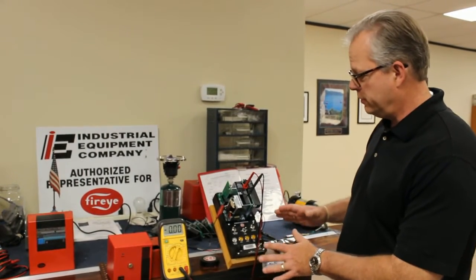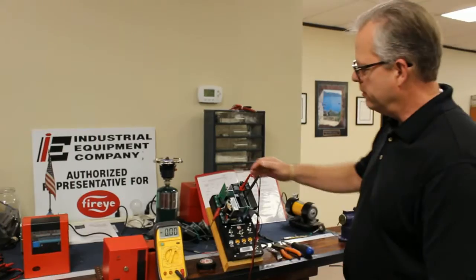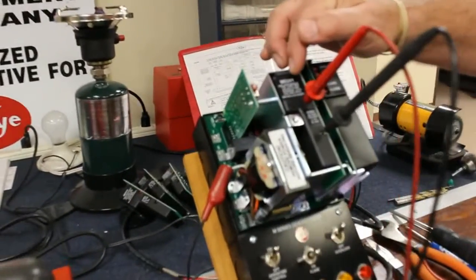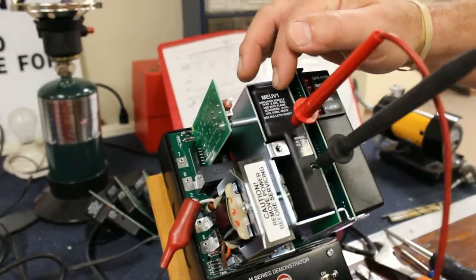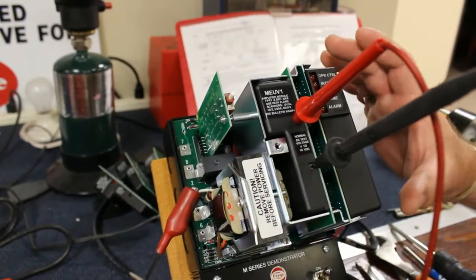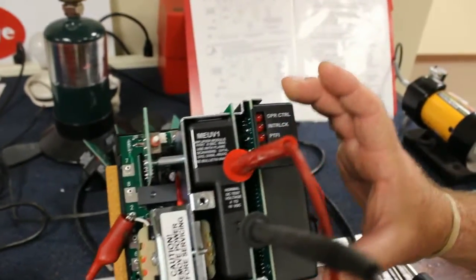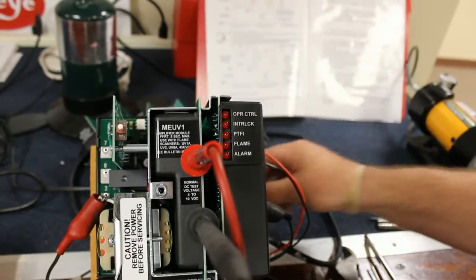but before I do, I'm going to talk about what we have here. We have an MEC120 chassis, an MEUV1 amplifier card that has a .8 second flame failure response time, and we have an MEP100 programmer in position, and I have it directly wired in to a UV1A3 scanner.